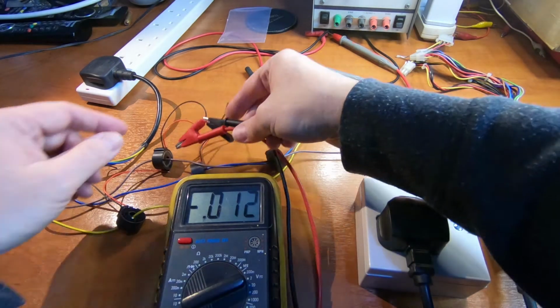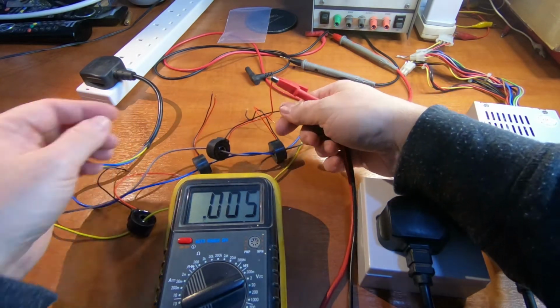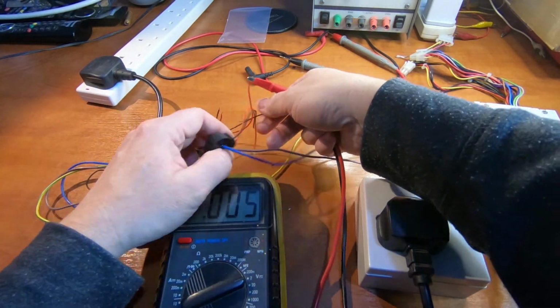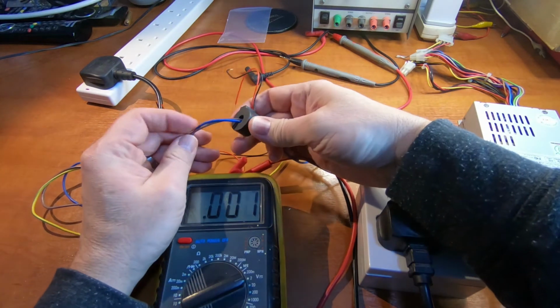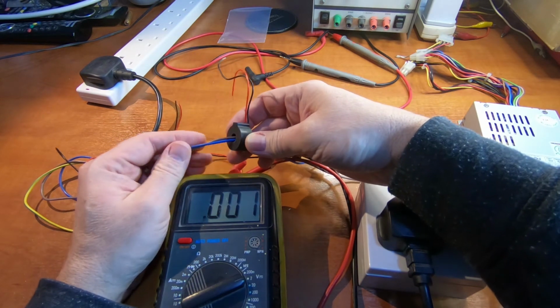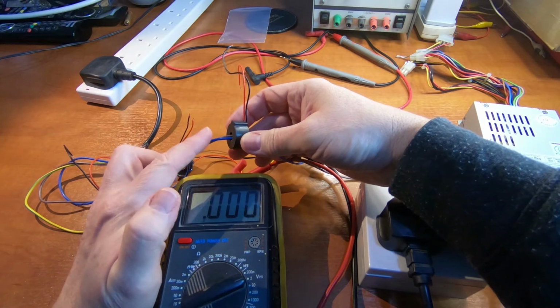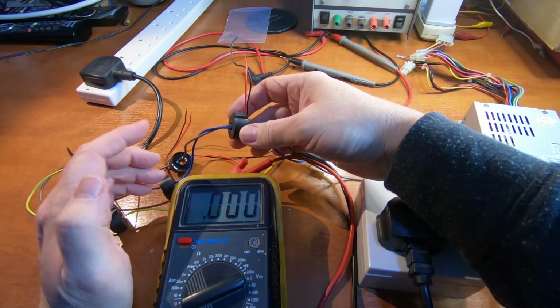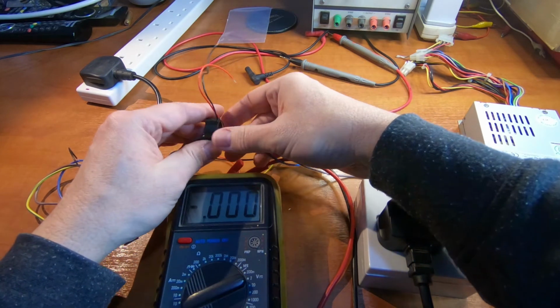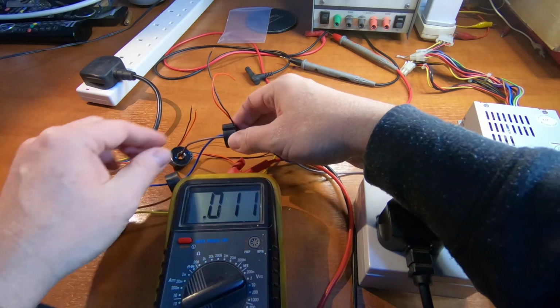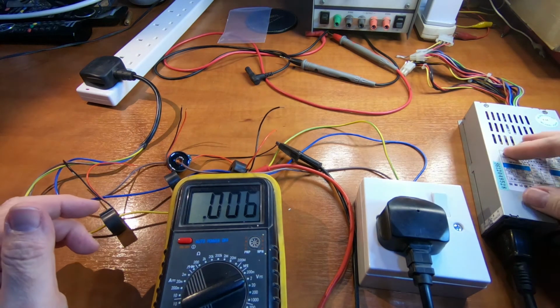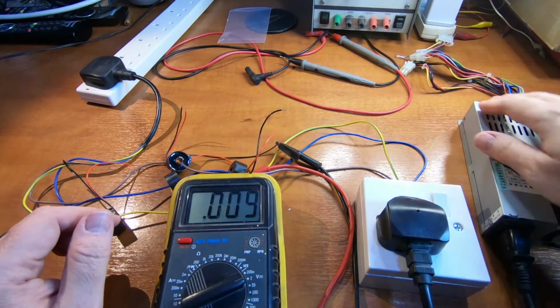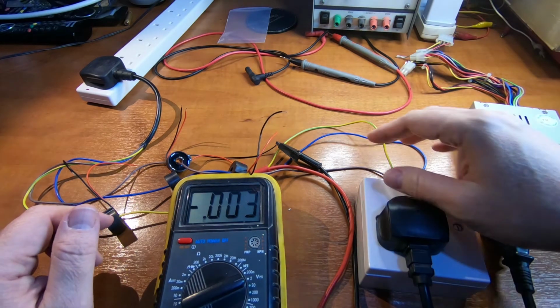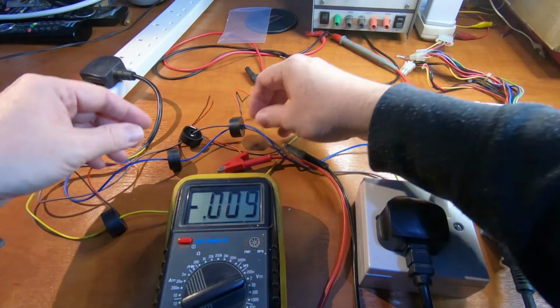So if I change this now to the twin conductors, the ones measuring the current on the live and the neutral, I'm expecting it to show 0, because the input current is matching the output current, unless there is some earth leakage on this power supply that I don't know about, but I'm expecting it not to be.